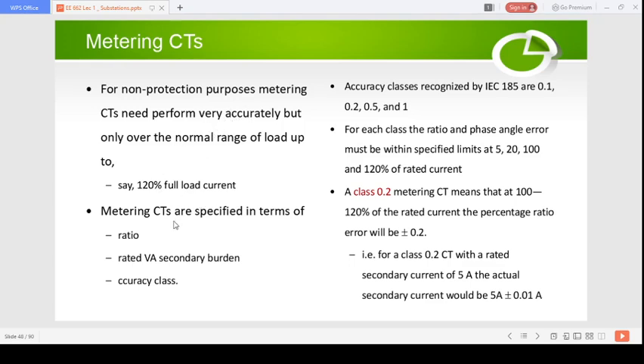Okay, so the metering CTs are specified in terms of ratio, rated VA secondary burden and the accuracy class. The accuracy class is recognized by IEC 185. The classes are 0.1, 0.2, 0.5 and 1.